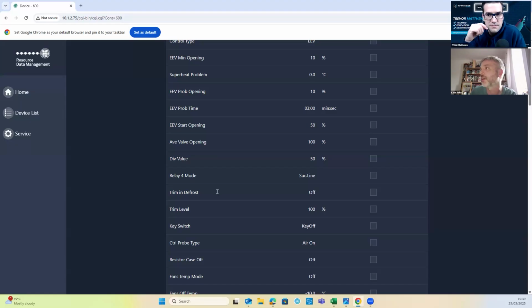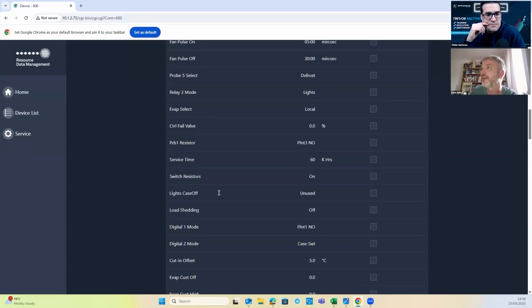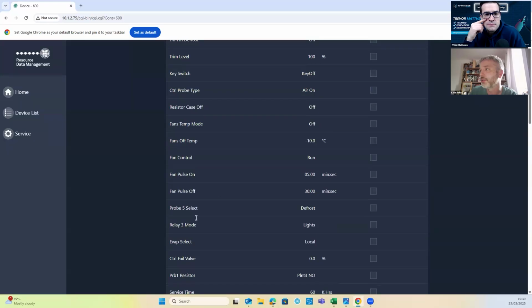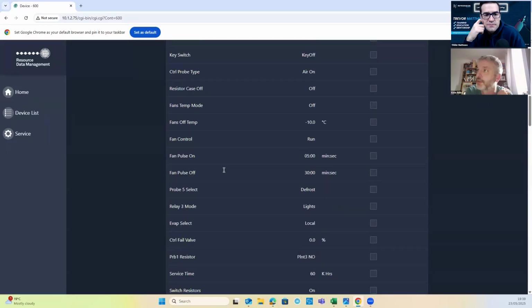So that's a really important one to use. What else? We've got loads of different settings for fans, for fan management, right? Yeah. So you can ask the fans to run all the time. You can ask the fans to stop when it stops cooling. You can ask the fans to stop on defrost.